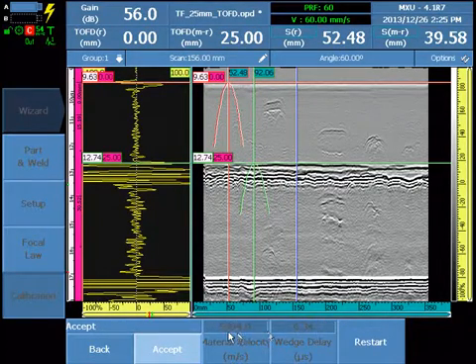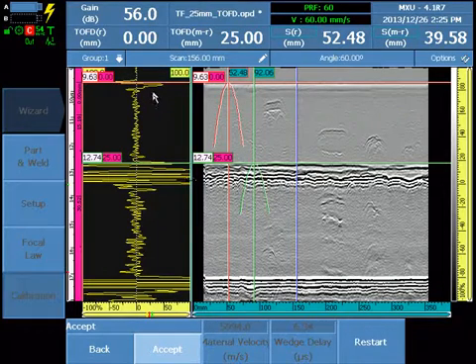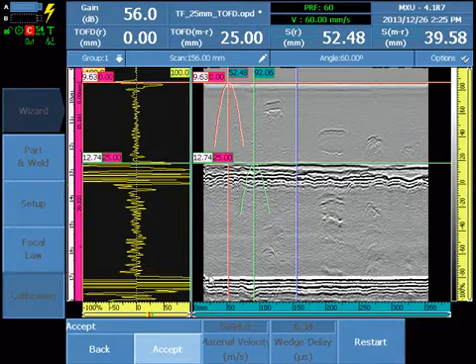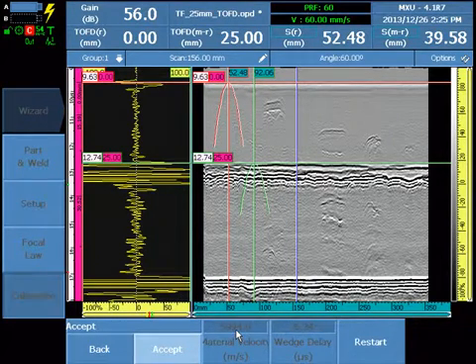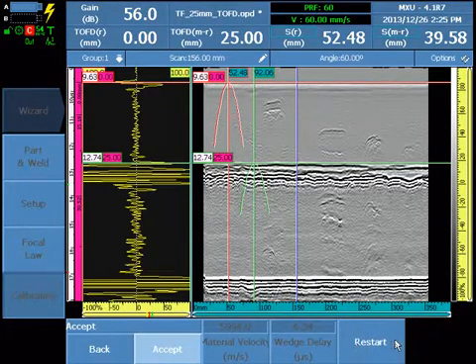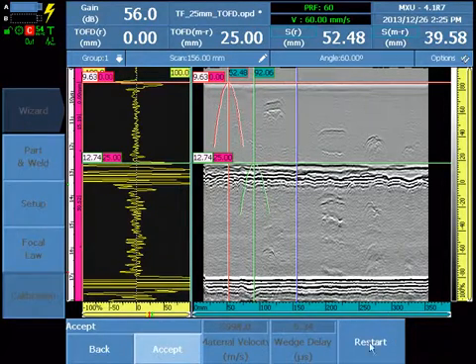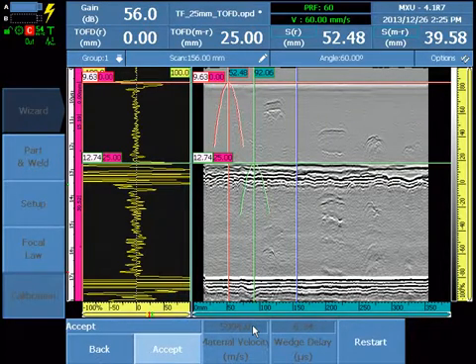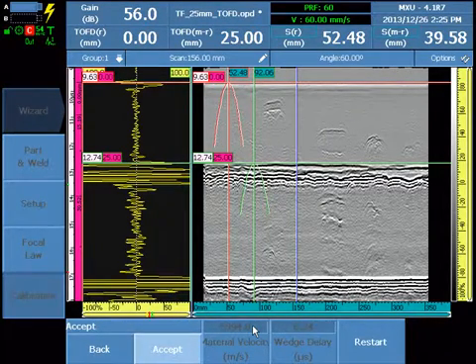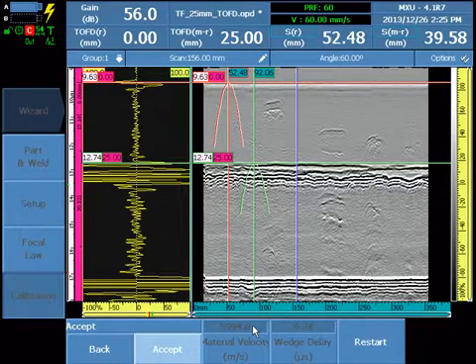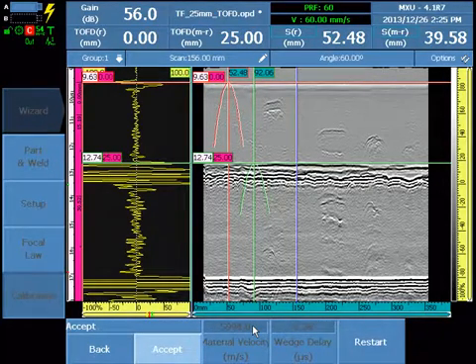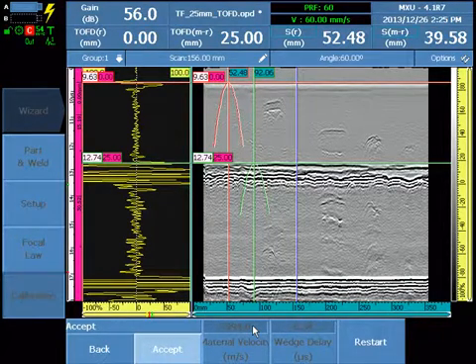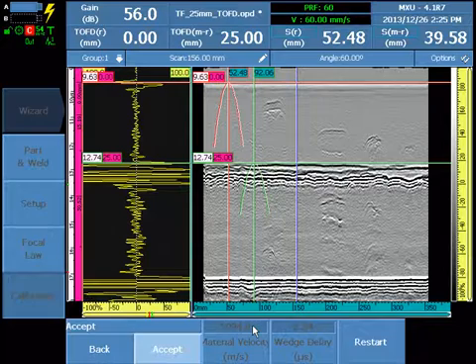If the velocity is accurate, validating that the position of the two reflectors used for the calibration are correct — in most cases we will accept the default velocity and not use the calculated. It is highly recommended that the velocity not be calibrated through the TOFD data, and if a real measurement is not available using pulse echo multiple back walls, that the default velocity in the database is used.